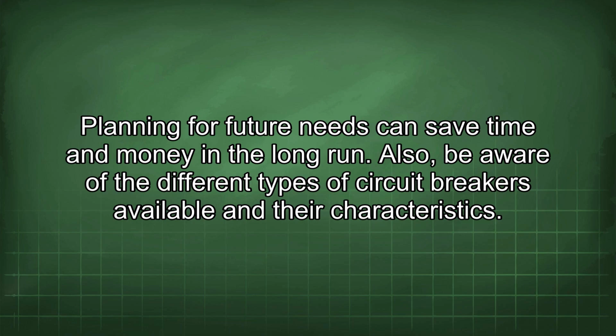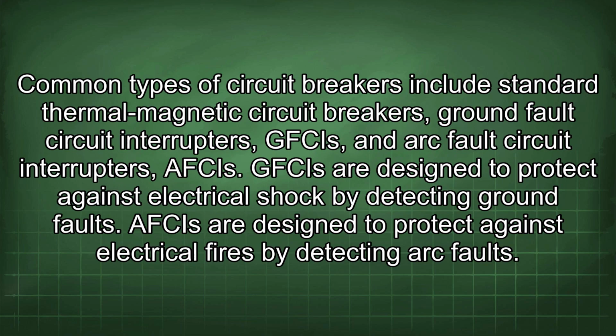Also, be aware of the different types of circuit breakers available and their characteristics. Common types of circuit breakers include standard thermal-magnetic circuit breakers, ground fault circuit interrupters (GFCIs), and arc fault circuit interrupters (AFCIs). GFCIs are designed to protect against electrical shock by detecting ground faults. AFCIs are designed to protect against electrical fires by detecting arc faults.